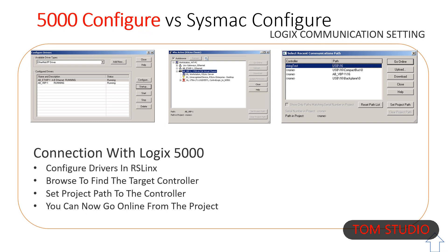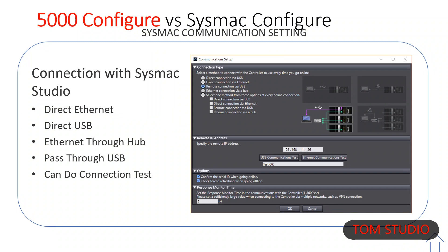In Sysmac Studio, you select the connection method in the project. If opening a project from a controller, the 'select one' option is not available. Enter an IP address if using Ethernet via hub or remote via USB. If you choose the 'select one' option, you are prompted to choose every time you click to go online. Both USB and Ethernet use CIP and HTTP.